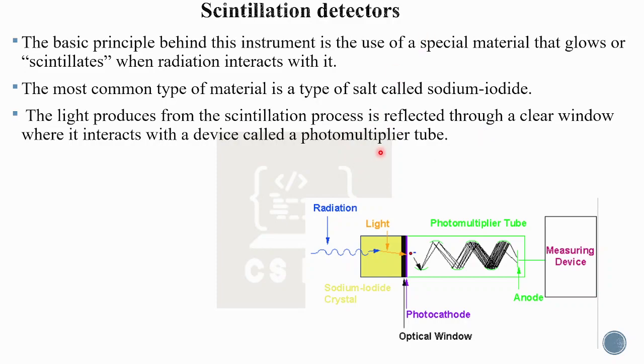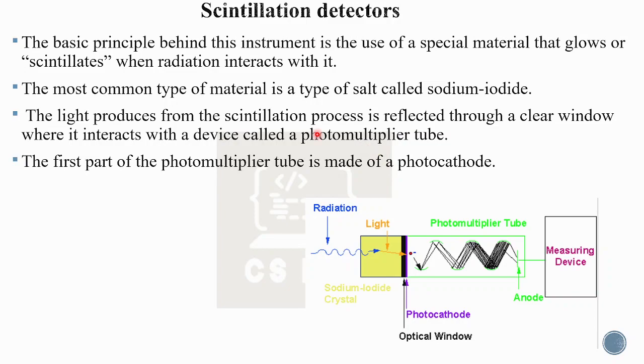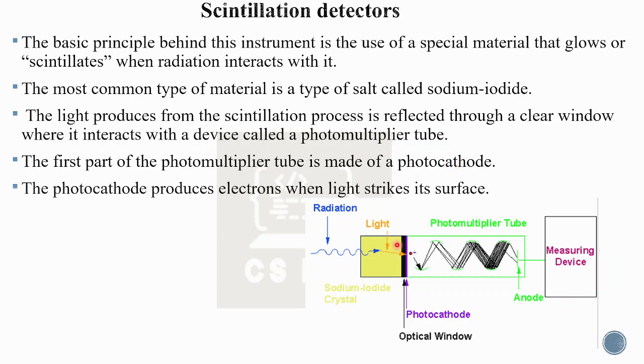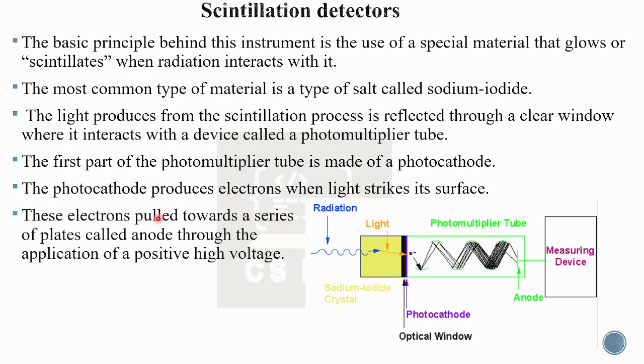The light passes through a clear window where it interacts with a device called a photomultiplier tube. The first part of the photomultiplier tube is a photocathode. The photocathode produces electrons when light strikes its surface. These electrons are pulled towards a series of plates called anodes through the application of a positive high voltage.